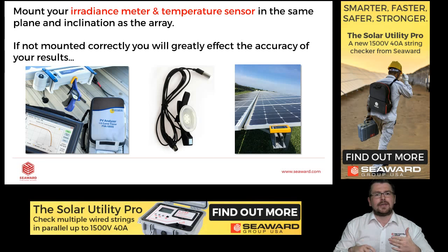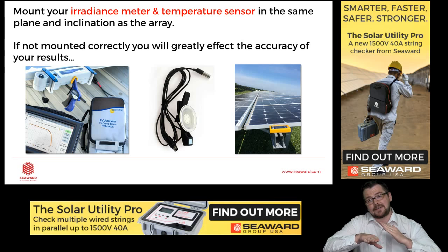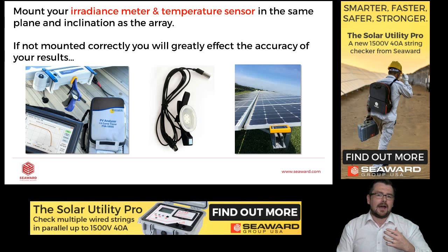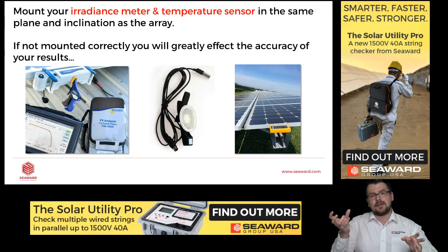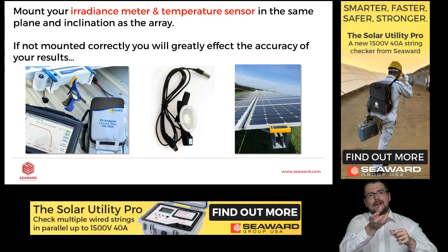So we should make sure that this is in the same inclination and azimuth as the PV array that we're testing in order for us to get the most accurate results. Seaward Group, we offer a suction cup. This goes on the back of the solar panel and attached to it is a thermocouple, and this is where we get the cell temperature.